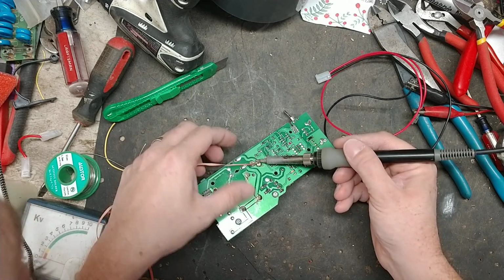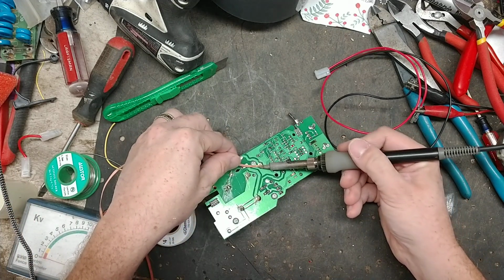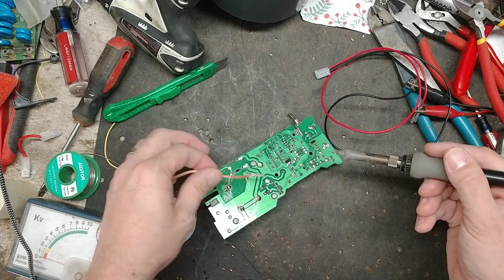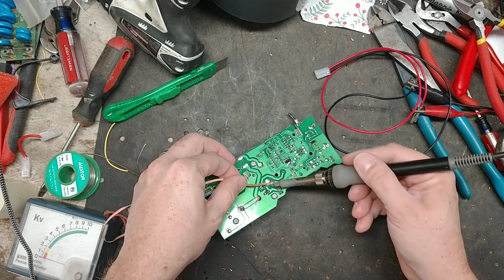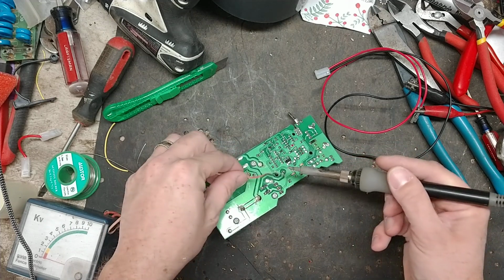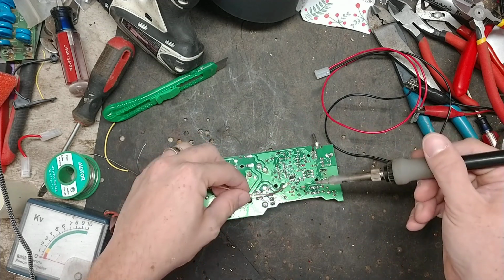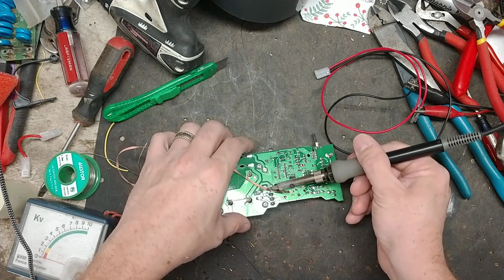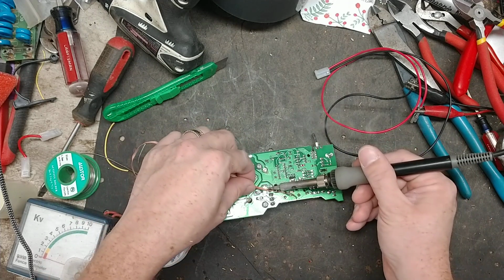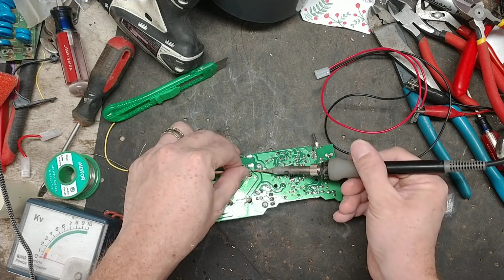But we are going to upgrade this unit here, this board, electronically. We're going to change the capacitor out to the next size bigger. And we do stock most of the parts here for this thing. We even stock new boards. So if your board's all water damage, because water got in it because your rubber switch cover was all rotted off or something, we do stock new boards here. We don't use them that often, but we've got them here just in case.